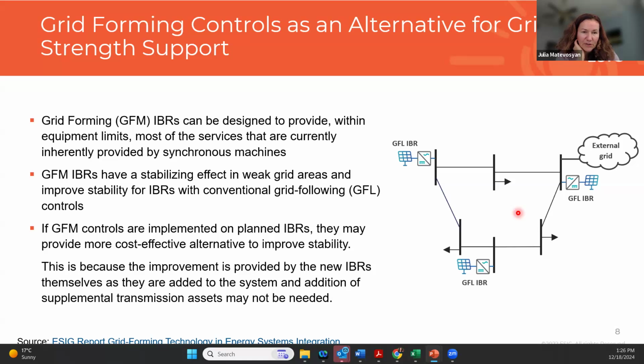Grid forming inverter-based resources have a stabilizing effect in weak grid areas, and they can improve stability for conventional grid following inverter-based resources. So if you think about it, if we could implement grid forming controls on the inverter-based resources that are going onto the grid in the next few years, they can provide a cost-effective alternative to, for example, synchronous condensers or new transmission lines to improve stability. In this case, the improvement is coming from the new inverter-based resources themselves as they are being added to the grid, and so you are avoiding the need for additional transmission assets to improve stability.